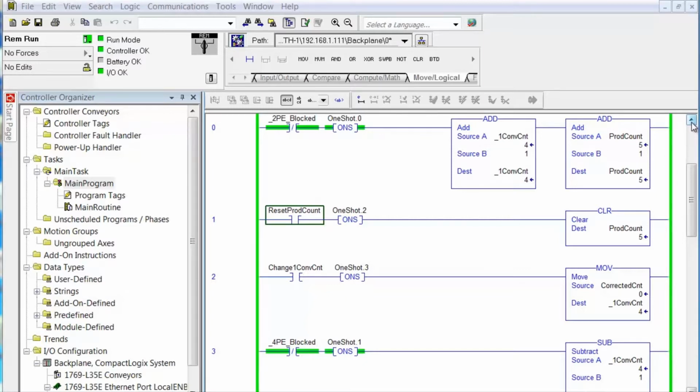So when you look at the graphics, it says there's 4 on it, but when you look, you see less than 4, which means that if you let this continue to run this way, it's never going to have 4 on there. So the system's not functioning correctly. So what you can do is enter in the corrected amount.